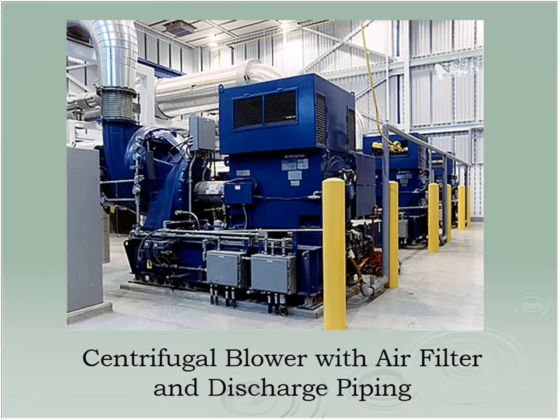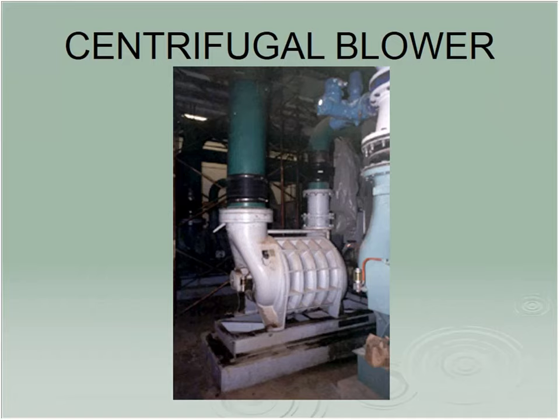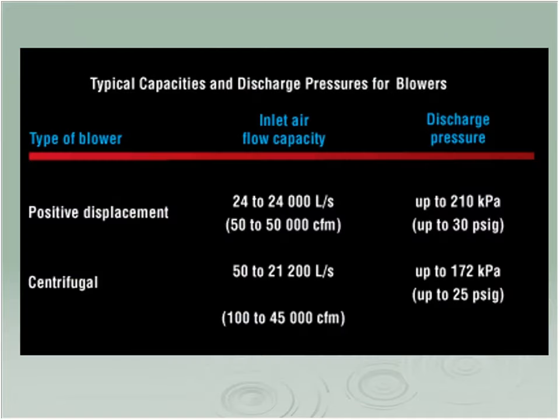Big motors. Upper Blackstone, where I do most of my training, has three 800 horsepower blowers. I don't want to pay that electric bill. The centrifugal blower, again, this one's a little more forgiving, and they actually open and close the inlet vanes to control the airflow through these. Multi-stage centrifugal. PD blowers, we're talking a lot of air, upwards of 50,000 CFM per unit. And up to 25 to 30 PSI, so some pressure concerns when you're dealing with these things.